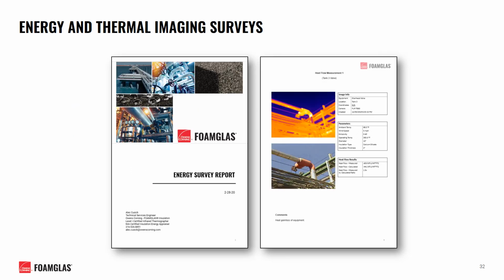We also provide on-site support around process improvements and energy savings. We have multiple certified thermographers on staff, myself included. We can arrive on site to perform infrared inspection surveys and conduct heat flow measurement and analysis. We can then issue a current insulation condition report, evaluate energy losses and savings potential, and provide advice on insulation system improvements to consider.